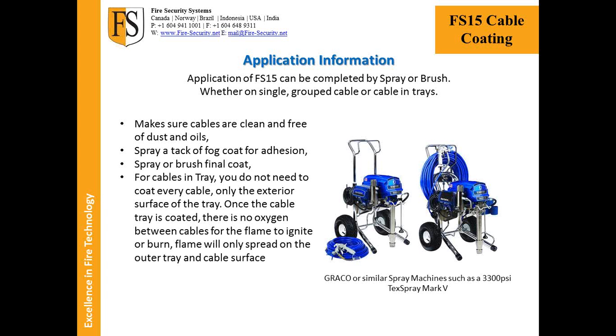It needs the fuel, which is the cable. It needs the oxygen, and it needs the heat, which is the fire. It's a typical fire triangle scenario. You take one of those things away, and we take the fire away because it can't breathe. There's nowhere to spread, and we take the oxygen away because we have the chemical reaction. So it's simply got nowhere to go.